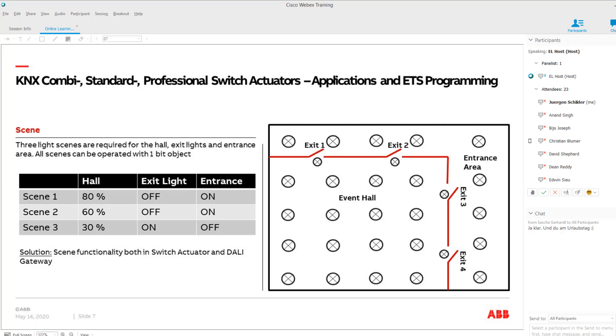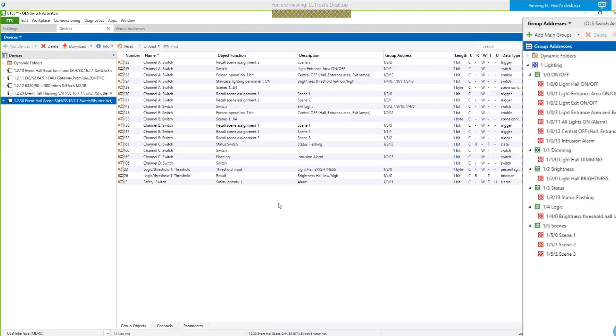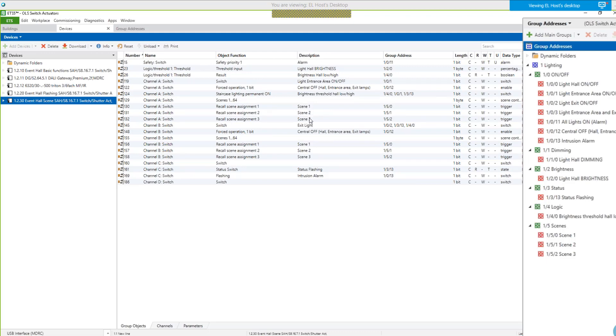I use a scene functionality both in the switch actuator and also the DALI gateway — the so-called one-byte light scene management. But to recall the scenes, I would like to have not only the one-byte objects where you have the information to recall or store the scene and the scene number, but also a simple one-bit object to activate each scene, which is possible in both devices. I have added the scene functionality in another component. You will find further group objects and parameterization for scenes — scene one, two, three for the different channels, as individual one-bit objects.